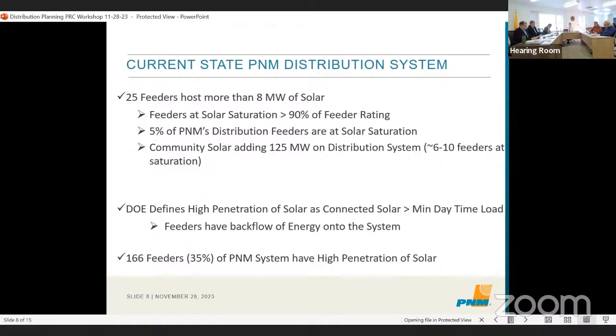On the PNM system today, we have 25 feeders with more than 8 megawatts of solar connected. When we talk about feeders at solar saturation, or at capacity, those are feeders where more than 90% of the feeder rating has interconnected solar. That's 25 feeders, about 5% of our distribution feeders. The community solar application is going to add another 125 megawatts at the distribution level. We're estimating somewhere between 6 and 10 more feeders will reach solar saturation after we interconnect these community solar projects.